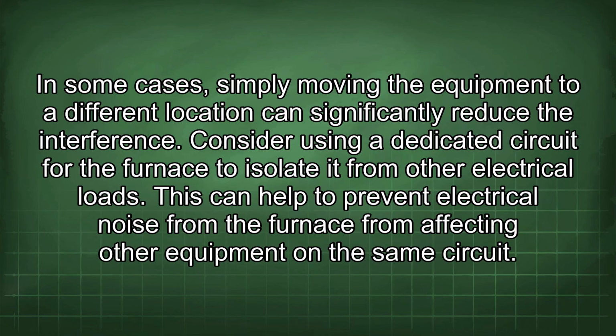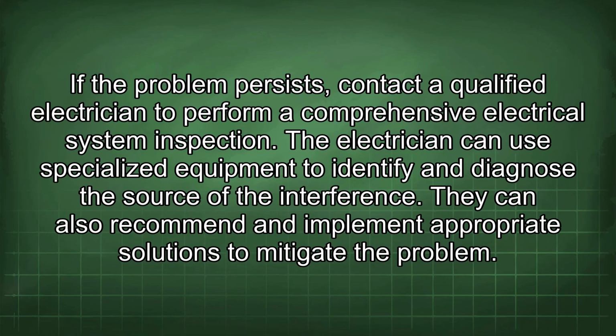Consider using a dedicated circuit for the furnace to isolate it from other electrical loads. This can help to prevent electrical noise from the furnace from affecting other equipment in the same circuit. If the problem persists, contact a qualified electrician to perform a comprehensive electrical system inspection. The electrician can use specialized equipment to identify and diagnose the source of the interference. They can also recommend and implement appropriate solutions to mitigate the problem.